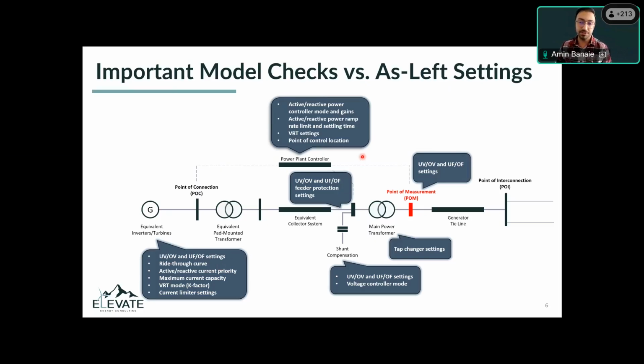Then moving to the PPC, it's good to look at the active and reactive power controller gains and what type of controller is used. If there is any ramp rate limit or settling time on the active power or reactive power, this is for requirements R2.4 and R2.5. Also the VRT settings of the PPC and where the PPC is controlling different quantities. We've seen a lot of cases where that control point is not accurately set in the PSSE model. Let's say the PPC is controlling POM or POI, but it's the other way around in the PSSE model. So we want to make sure that all of those match what's in the field. And also for the MPT, the tap changer setting is very important: which side of the MPT that tap is controlling, and what the default setting in the field is for that tap.